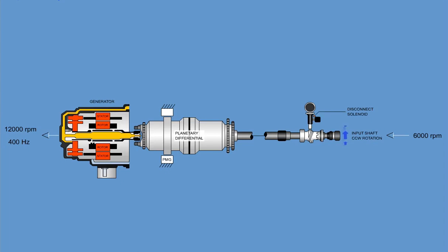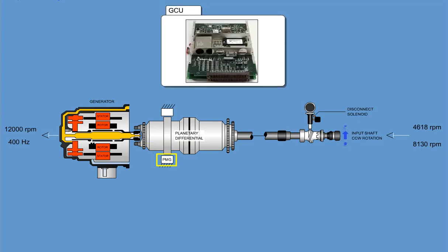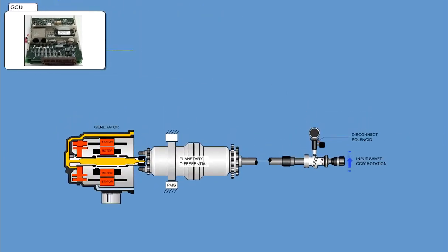The IDG is able to achieve this constant generator drive speed if the input speed is between 4,618 RPM, which is the minimum idle speed, and 8,130 RPM. This varying speed deviation from 400 Hz generates, via the permanent magnet generator, associated electrical data to the Generator Control Unit, GCU. The GCU supplies an electrical signal to a servo valve inside the CSD.